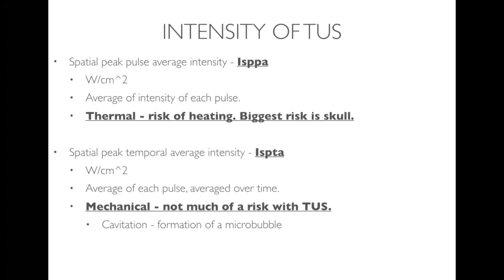These measure, more or less, two separate things. The ISPPA measures the thermal effect, and the ISPTA measures something I call the mechanical effect. When you deliver ultrasound to something, it can do two things: it can cause it to heat, or it can cause the surface to vibrate a little bit. The ISPPA measures the risk of heating, and the ISPTA measures the risk of something called cavitation.